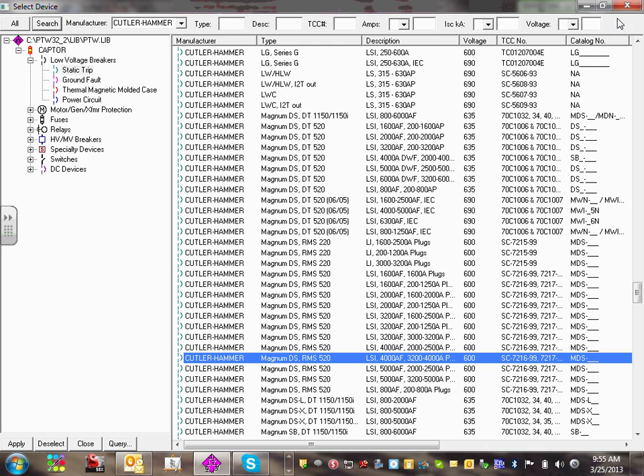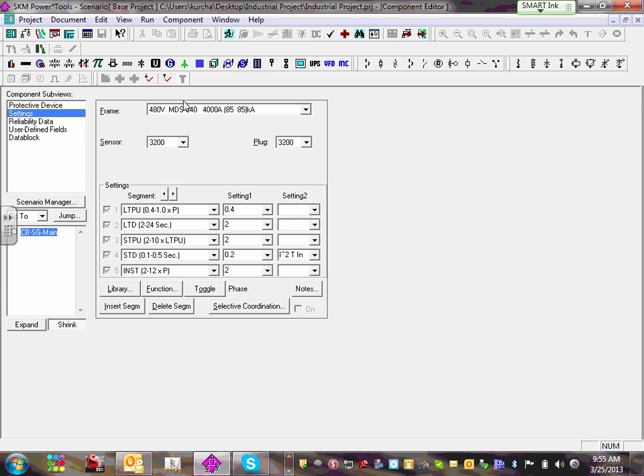Make sure it's the 4,000, close on that. When you come over here, you're going to find and grab a 4,000 amp sensor. We know what the sensor is now. And make sure, Jeff, that you set the circuit breaker at 1. Make sure the sensor is 4,000 — we know what the sensor is. We go to your plug, make sure your plug is 4,000, and make sure your setting is set at 4,000. That's all you need to do. If you did that, you're good to go. Cool? Everybody okay with that? Yes? No?